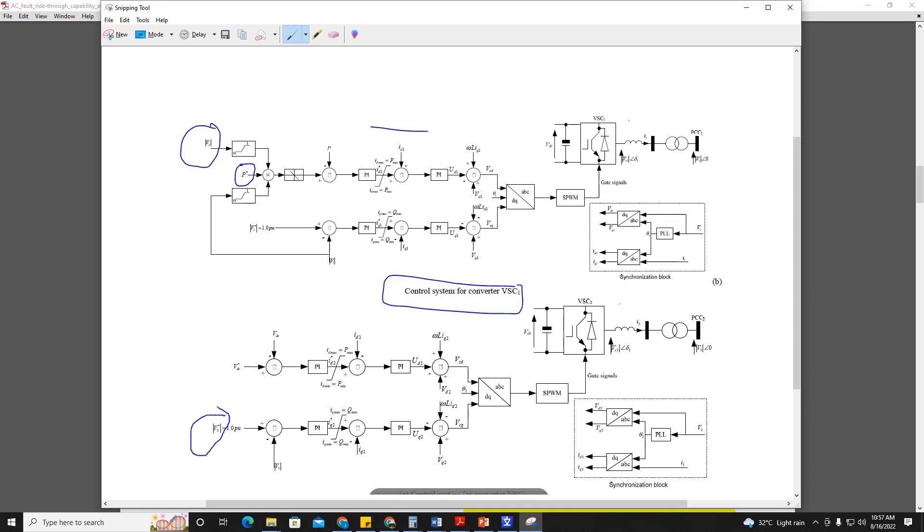If there happens any change, any dip, any interruption in AC voltage at point of common coupling, then accordingly the changes will be made into the active power reference to ensure that fault ride-through technique is happening. Here we can see that converter station 2 is responsible to control the DC voltage, so this is the outer loop control for DC voltage and AC voltage, whereas converter station 1 is responsible for controlling the active power and AC voltage. Changes in active power will be made depending upon the point of common coupling voltage at converter station 1 V1 and converter station 2 V2. So if there will be some problem, accordingly the power will be adjusted.